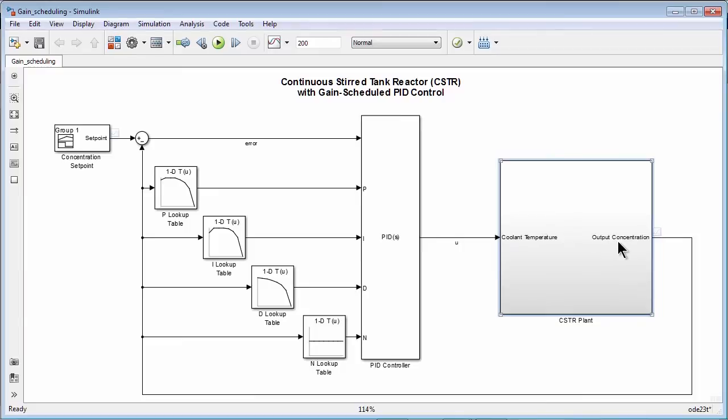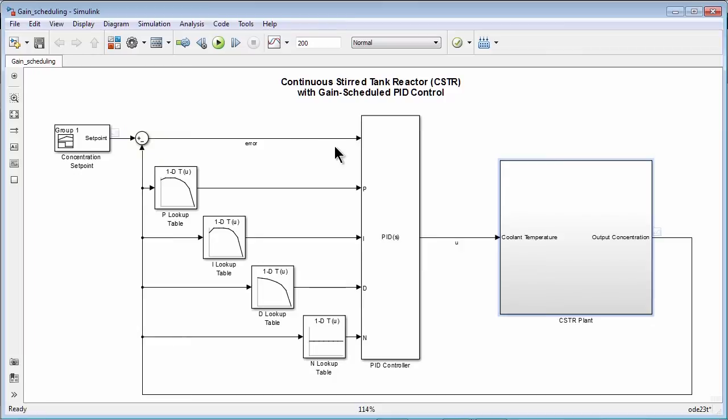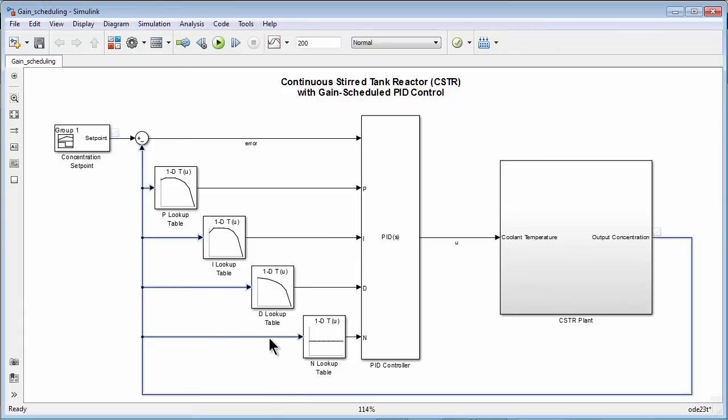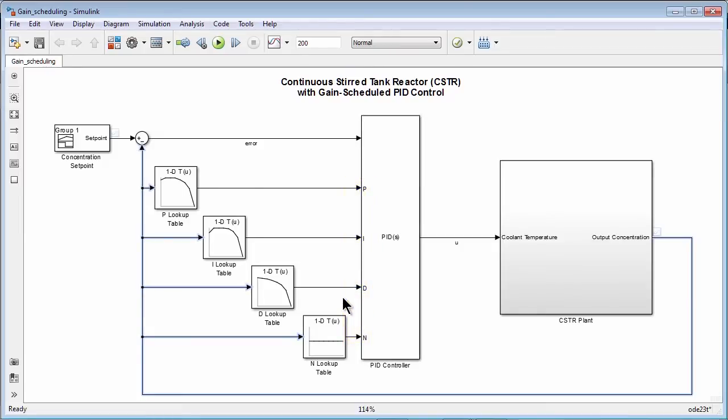We take the output concentration and feed it back to the summation junction, where we subtract the output concentration from the setpoint value. The error signal goes to the PID block. We also use the output concentration signal here to drive the gains of the PID controller. They are now going to change at different operating conditions, and they are going to change according to this lookup tables here.